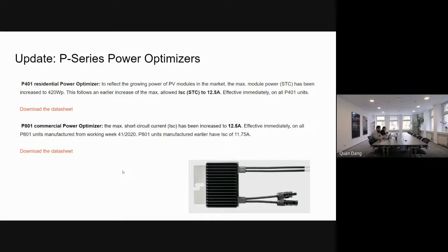Okay, so let's start with P-series. You know we have a lot of P-series optimizers. Last month, SolarEdge updated the P401 and P801. Originally, P401 could be used with modules up to 400 watt peak; right now it could be used up to 420 watt peak, with a short circuit current of 12.5 amps. So basically they extended it a bit so you can use it with bigger modules. The message is all P401 units will be updated like this, no matter where they're produced.